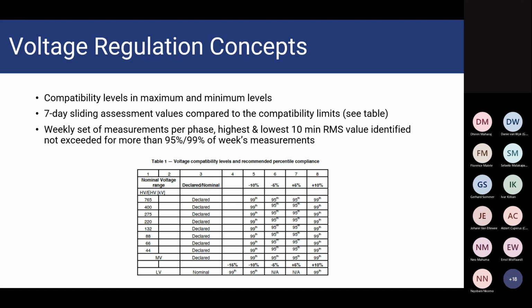Okay, so the compatibility levels in this table define the maximum and minimum levels that we already mentioned. From version 2015 of the NRS 048, a 7-day sliding assessment value is compared to the compatibility limits. So your 95th percentile value, or your voltage RMS for 95% of the time in a 7-day window, is compared to the limits defined in this table. And that 7-day window changes every day. So it's a continual assessment value that's being compared, and I'll show you an example of how that looks on the next slide as well. Yeah, so that's basically how that works.